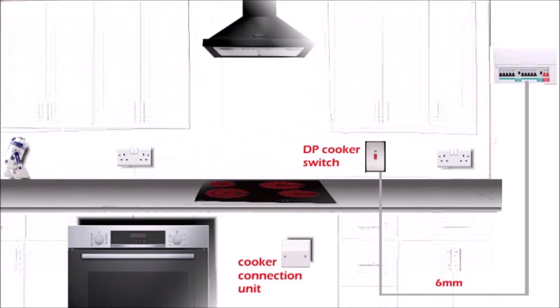You need to run 6mm twin and earth cable from the consumer unit to the double pole cooker switch, and also 6mm twin and earth from the cooker switch to the cooker connection unit. At the consumer unit, usually a 32 amp MCB is enough, but sometimes you need a 40 amp MCB — it just depends on the load you're going to connect to the circuit.